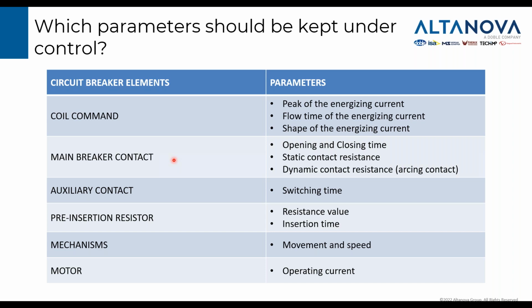It's possible to add some transducers in order to test the movement of the main leverages and also the speed of the movement. Circuit breakers must operate in the fastest possible time. And for the motor, we can use, for example, current clamps in order to check the operating current of the motor.